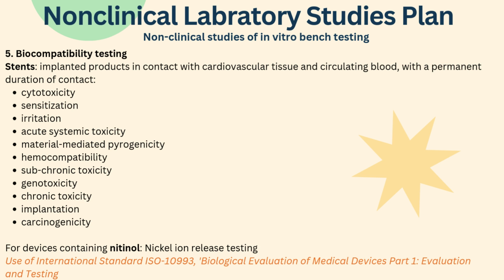So, the different tests we will use will assess both the local and systemic biological responses, and this includes cytotoxicity, sensitization, and irritation, which again will just ensure that the materials are not causing any cellular damage or adverse tissue reactions. Now, on the flip side, going more systemic wide, these will be evaluated through acute, subchronic, and chronic toxicity testing, while genotoxicity and carcinogenicity assessments will address the longer term risks that are associated with the permanent implantation of this device.